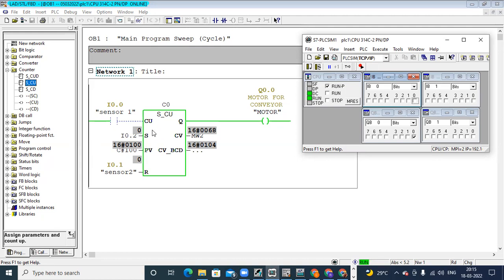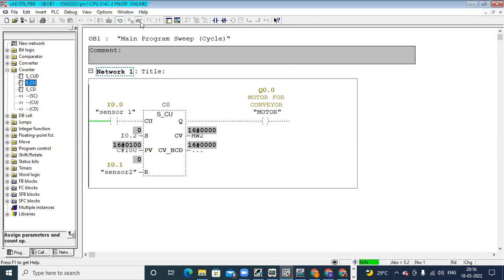A practical example: a packing machine counting number of boxes packed. If the machine was already at 500 and that last value is stored in memory, you want to start counting from 500 rather than the beginning. So you use set and PV to set that value directly, then from 500 it starts counting 501, 502, and so on. Here I have taken 100 as the example. If you do the reset input, it will reset to 0.